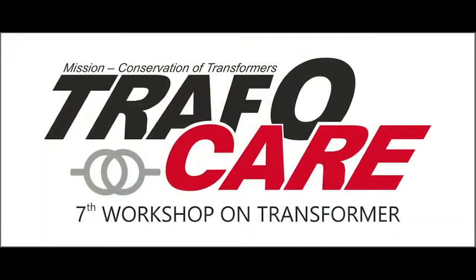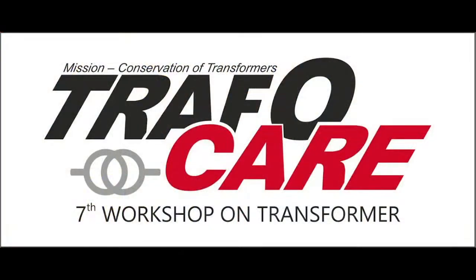Yeah. Okay, ma'am. Another method is adopted in 400 kV. Sir, in the open delta, each phase you provide a PT, and on the secondary you observe the open circuit delta voltage. If the open circuit delta voltage goes high, then it will trip. So that is another protection available. You mean voltage based protection to be taken in the circuit to trip the transformer? If there is any unbalance or fault in the tertiary winding, the open delta voltage will go above 50 volts, I think. But the way you're talking is about mechanical weakness, you should check it because tertiary is very vulnerable to such faults. So you should be aware of the condition.